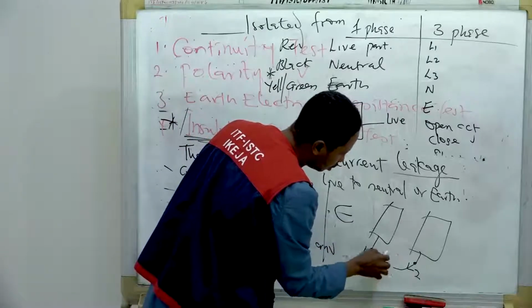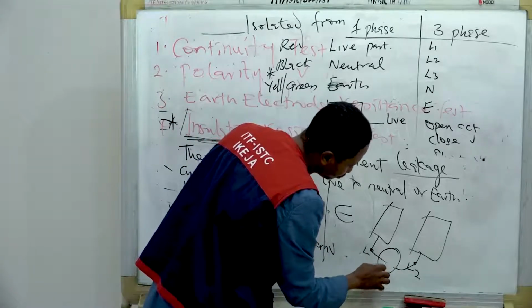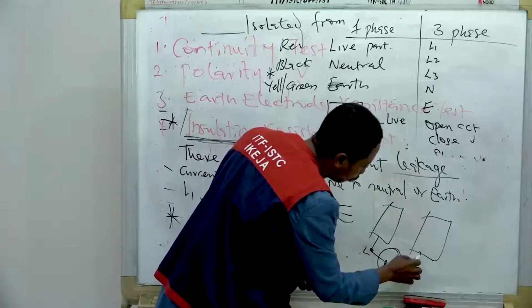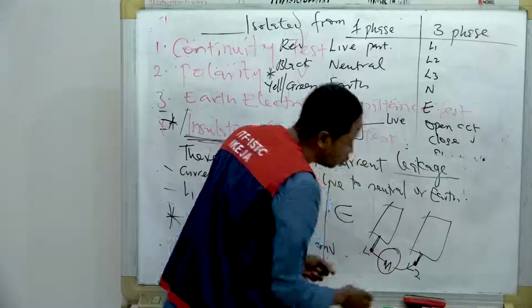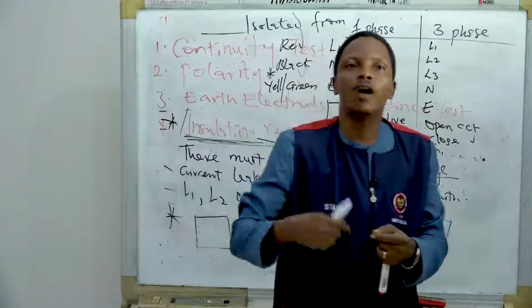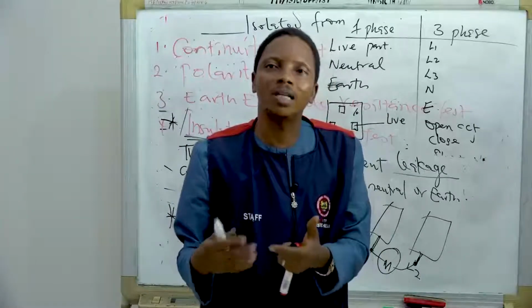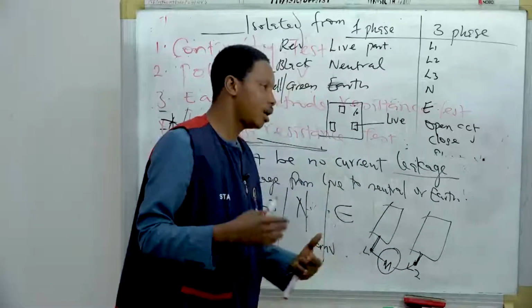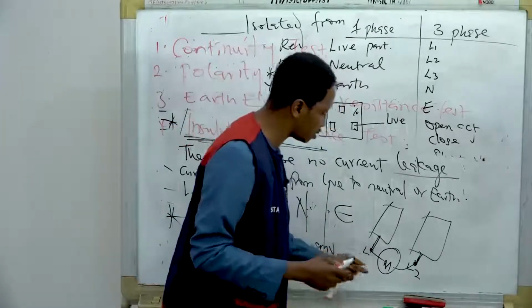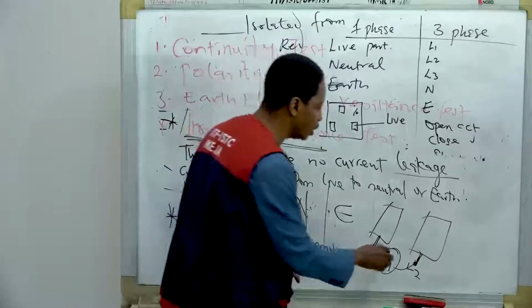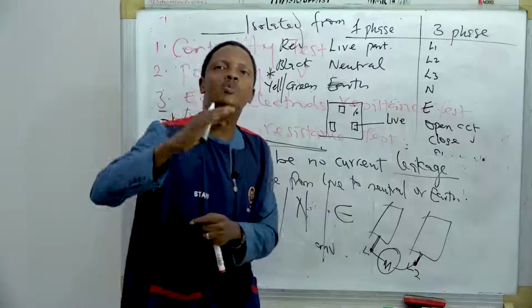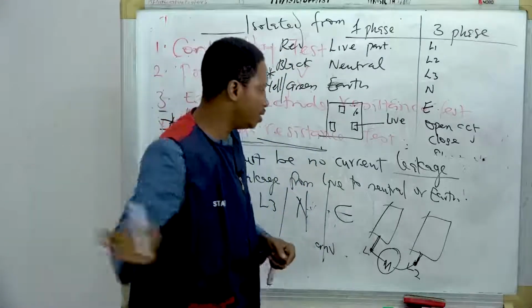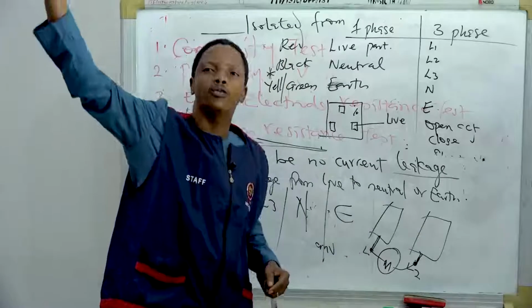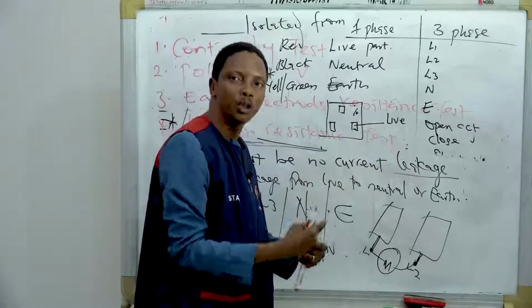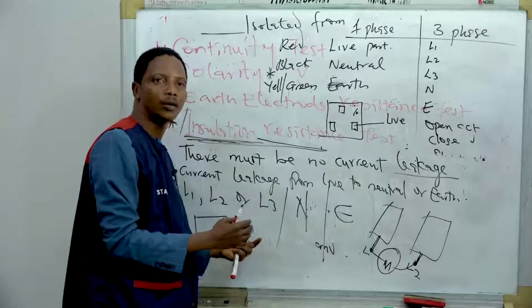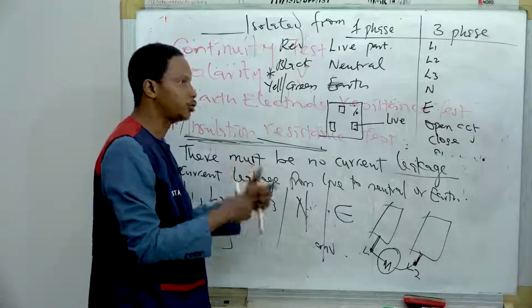You put it, this is my megger tester, and then the probe is connected to conductors 1 and 2. You now inject 500 volts, or 1000 volts, as it may be, depending on the capacity of the megger tester. There must be no leakage. If there is no leakage, the megger tester will be reading to infinity, reading from 500 mega ohms and above. But if there is leakage, it will read below. That reading going towards 0 means that there is leakage. Then you have to cross-check.